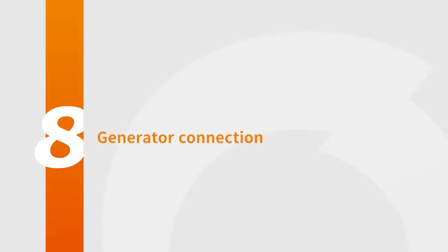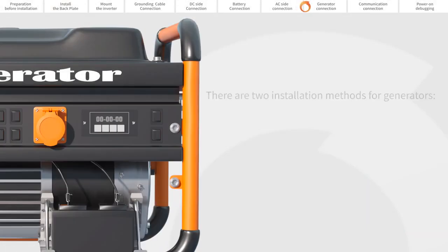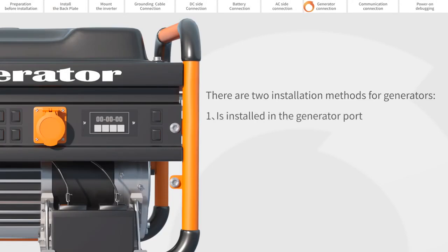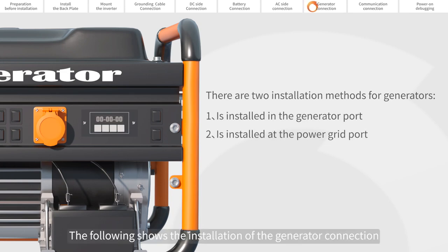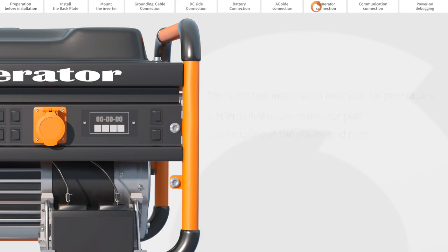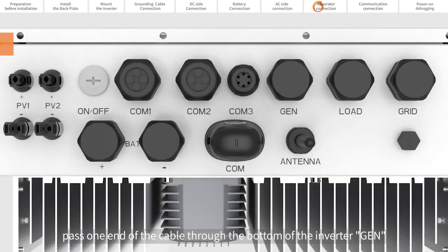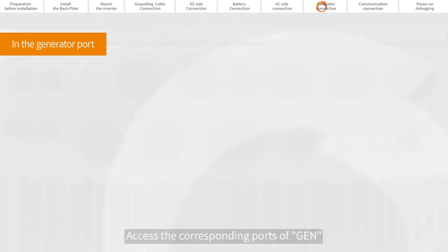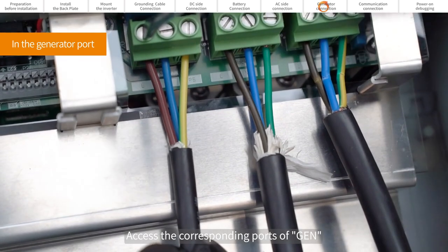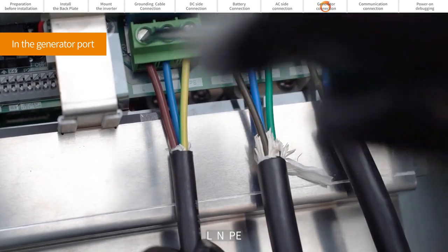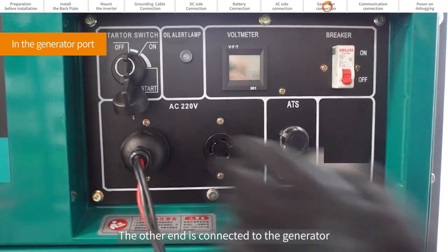Generator connection. There are two installation methods for generators. One is installed at the generator interface. Two is installed at the power grid port. The following shows the installation of the generator connection at the generator interface. Pass one end of the cable through the bottom of the inverter generator port. Access the corresponding ports of generator L, N, PE. The other end is connected to the generator.